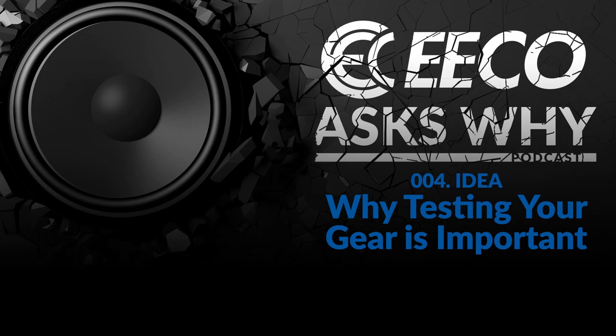By that I mean, if you have a system where you have an incoming 480 volt breaker, and then out of that panel it feeds a transformer, and then out of that transformer it feeds another panel board, and then out of that panel board it feeds some outlet somewhere. If you have a fault in that outlet, you do not want your 480 volt breaker to trip. Because if that 480 volt breaker trips all the way upstream, it's going to take out your entire facility. So you would want the breaker closest to the load to trip.